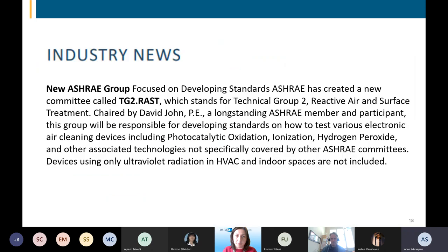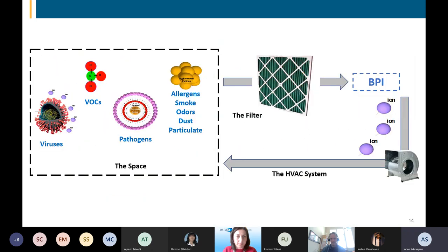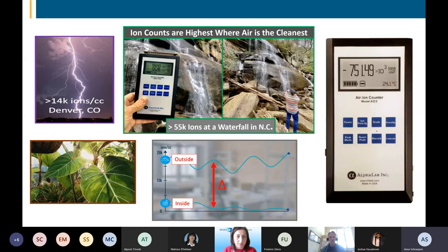Let me just go back to that slide just for fun so we can tee up the conversation, because usually people have a lot of questions on counting them. You most certainly can measure ion concentrations with a handheld, both indoors and outdoors in the space at the device, but handhelds can be cumbersome. So you as well can install devices that measure ion concentrations indoors, outdoors, in the space, in the ductwork, that can be hard mounted and wired back to the BAS as well.